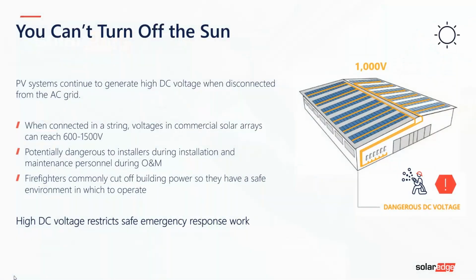As you know, you can't turn off the sun. Turn off a normal inverter, and what happens? Well, that drops down to 0 production, but there's still up to 1,000 volts on the roof. Should there be a problem, turning off a traditional inverter isn't going to help. But with SolarEdge, we can turn off the optimizers, turning off the panels, and therefore reducing it to a safe voltage. The maximum we declare is 50 volts for commercial, 25 for residential. But in real terms, because of design rules, you're looking at 30 volts for commercial and around 25 for residential, so you're not getting a huge amount of volts.